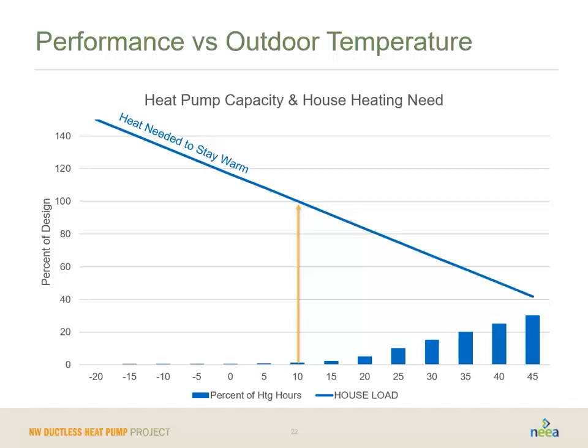So we're really talking about heating systems that need to be very flexible, to be able to, a lot of the time, only produce a little bit of heat, and maybe once in a blue moon, produce a lot of heat. And this is the nature of why modern heat pumps, these variable capacity systems, are so great: they can actually do a lot of this work. You'll notice that the temperatures of about 35, 40, and 45 represent something on the order of 65% of the hours in the year, and that's in the place where you only need 60% or less of your full capacity. That speaks to how good your system is at running at low heat and low speed. The better it is at that, the better the system will be at not having to turn on and off, creating comfort issues and potential issues with longevity of the equipment. So that's something we're really going to focus on moving forward.